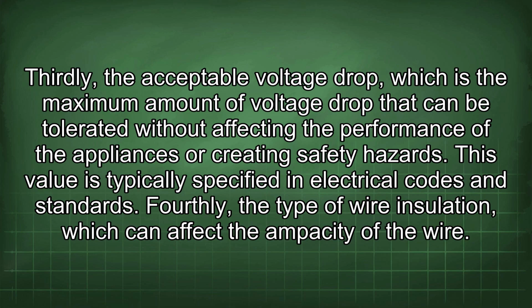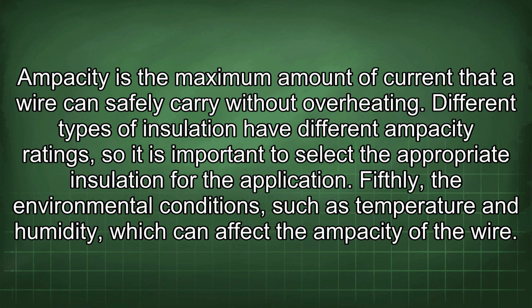This value is typically specified in electrical codes and standards. Fourthly, the type of wire insulation, which can affect the ampacity of the wire. Ampacity is the maximum amount of current that a wire can safely carry without overheating. Different types of insulation have different ampacity ratings, so it is important to select the appropriate insulation for the application.